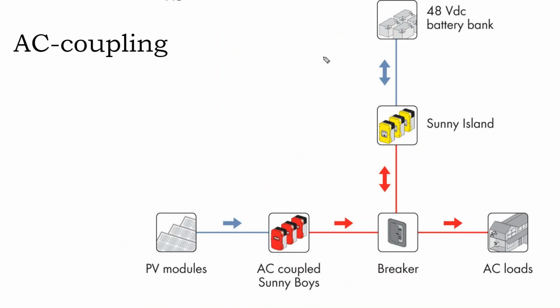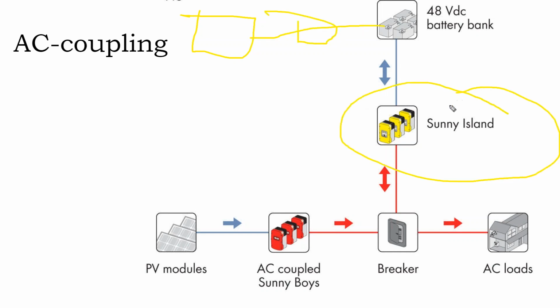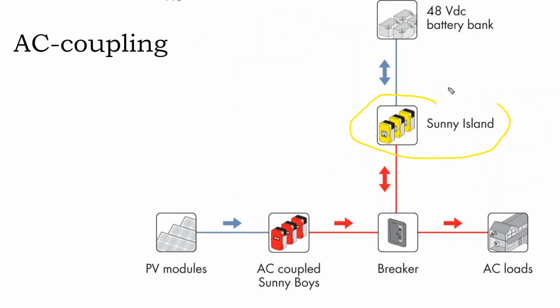The efficiency of the system—which is more energy efficient—is debatable, and the debate is a little nerdy because it's very close together; one system is not inordinately more inefficient than the other. The biggest difference I can find between AC coupling and DC coupling is that if the solar array is tied directly into the battery bank, you only have one inverter for the entire system, and battery inverters do more and are more expensive than solar inverters. So your output for the entire home is smaller, or at least more expensive.